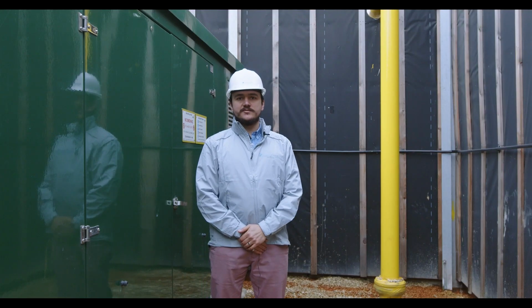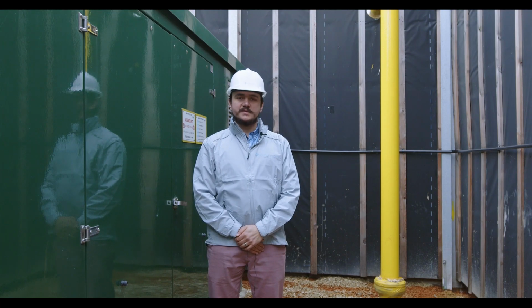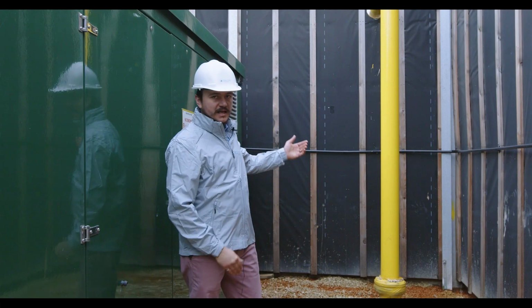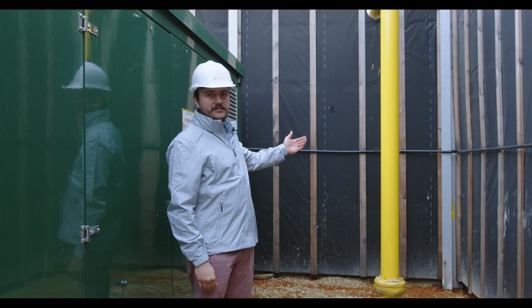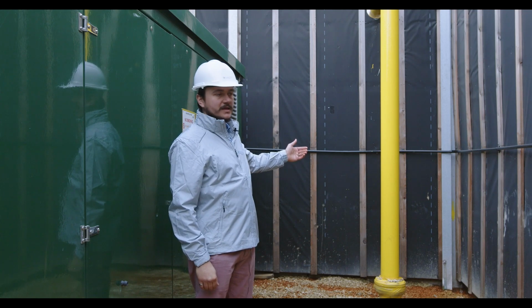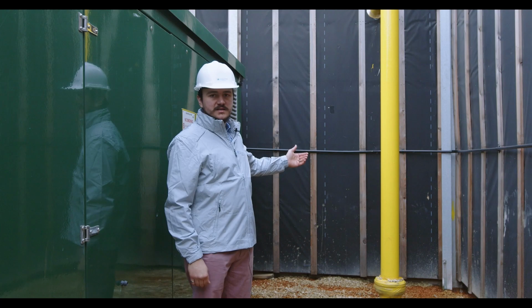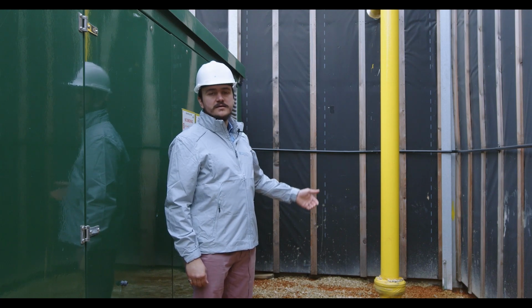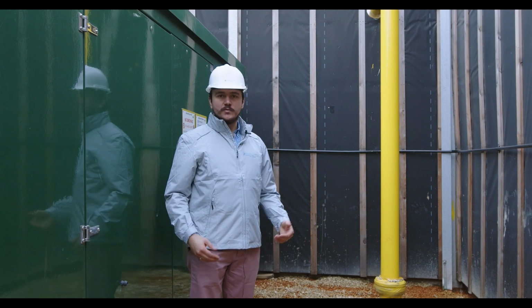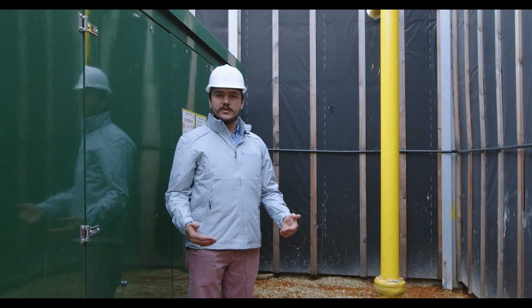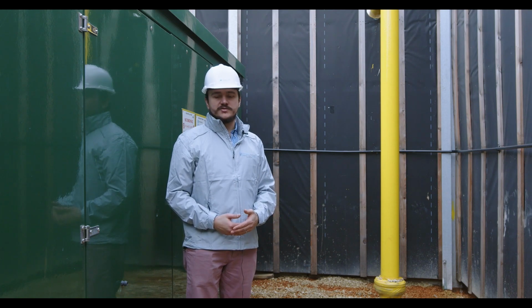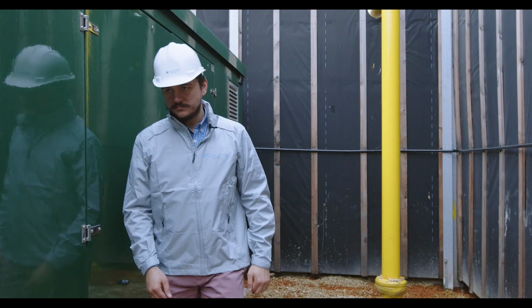What I'm now going to take you through is the operational life cycle of the gas peaking plant. As you can see behind me, the yellow pipe is how the gas enters the site from the local distribution network. The gas enters the site at intermediate pressure, which is too high for the engines to operate off. So what we use are pressure reduction skids to bring the pressure down to the operating pressure of the engines.